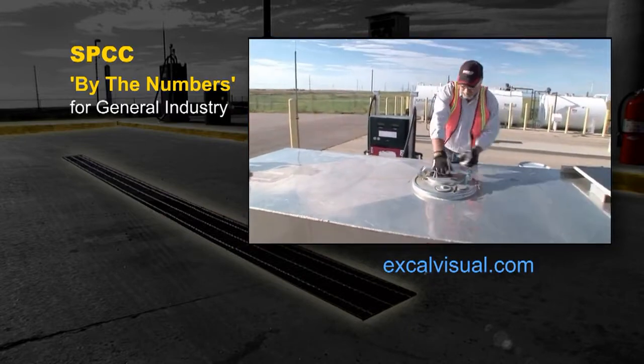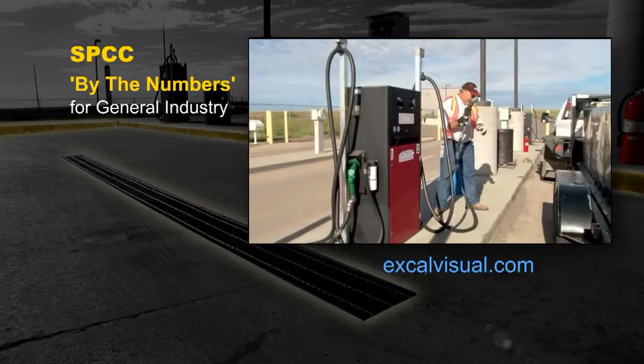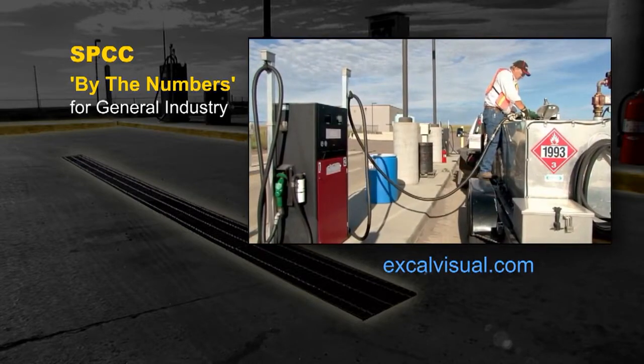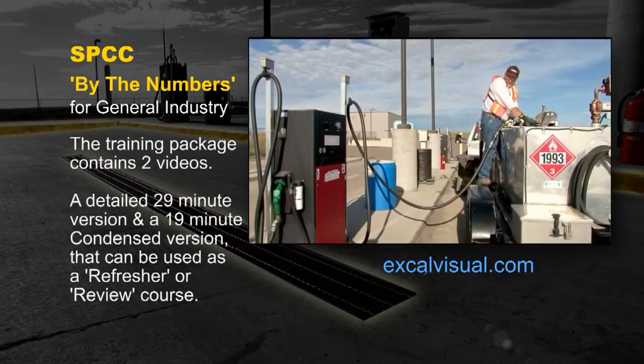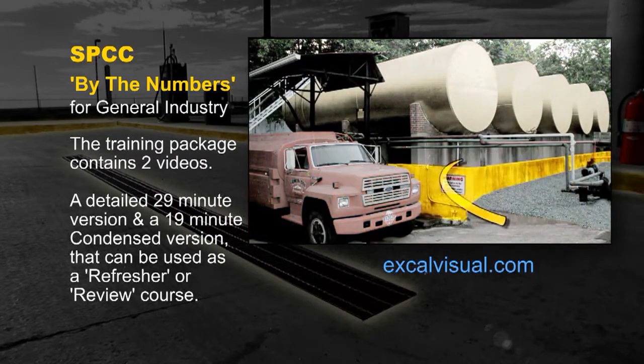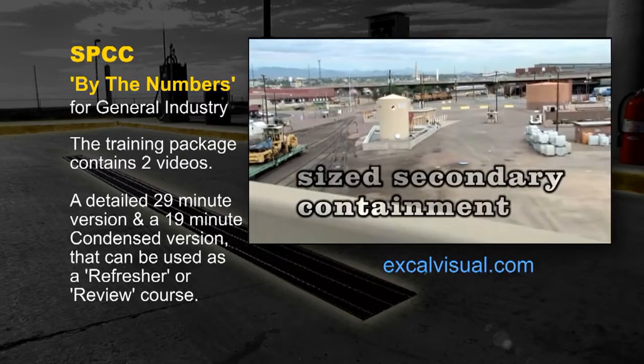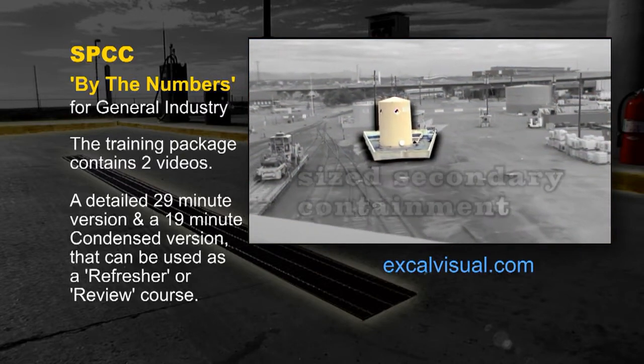Overfill prevention is also accomplished manually by watching the gauge, sight glass, or meter during a transfer. The operator or operators must know when to slow down or cease filling. In addition to the container itself, oil storage areas generally have an additional means of accidental discharge protection. The most common is called sized secondary containment. The concrete berms under and around this tank battery are a good example.